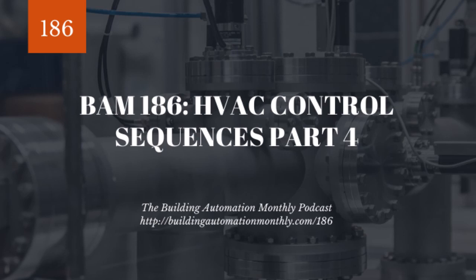But there's also mixed air temp control, in which we are either using a preheat or we are using an outdoor air damper. And I see a lot of folks mix this up, because what they don't realize is that there is both a heating component typically and a cooling component to mixed air control. The cooling component to mixed air control is typically using your economizer to drive your mixed air temp down. So you've got a mixed air temp set point, you've got a mixed air temp, and you're opening up your economizer to bring in cold air to drive the temperature down.